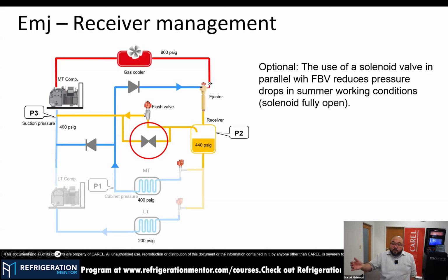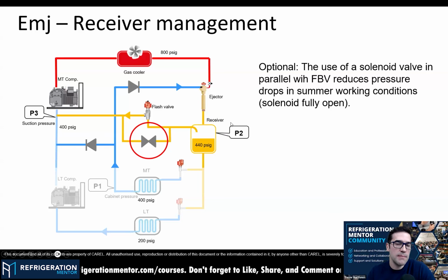With these sequences of operation and logics, you can consider, Trevor, that all the MT compressors in your rack will be operating as a parallel line. So that's another benefit: with this layout, this design, this CAREL technology, you avoid having a parallel compressor sitting there to operate a couple of hours per year. You could use your own MT compressor that's already there to maximize this efficiency. Yeah, and so this is more for the manufacturer side.